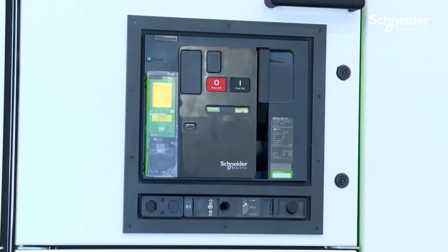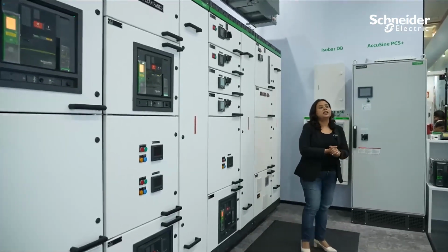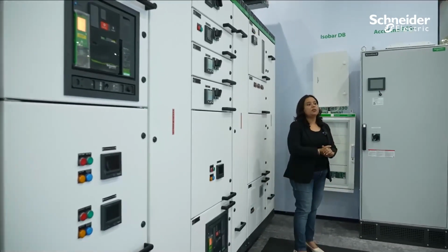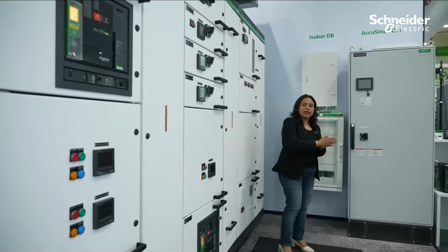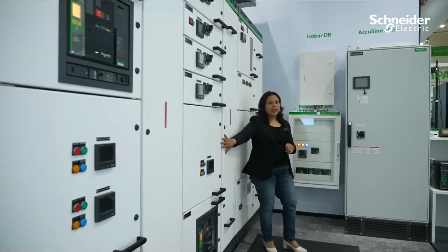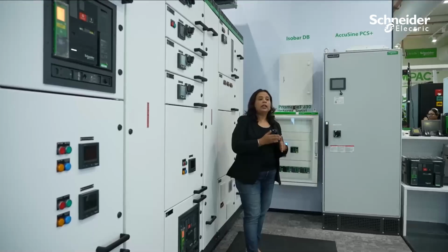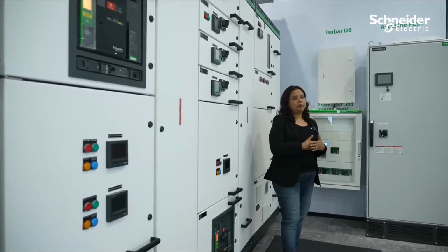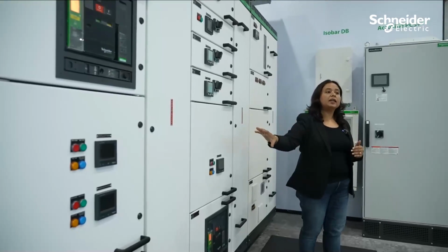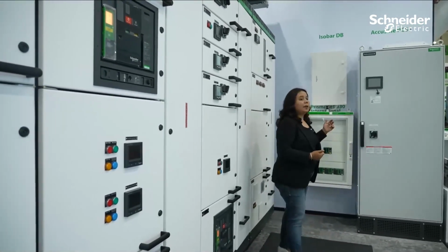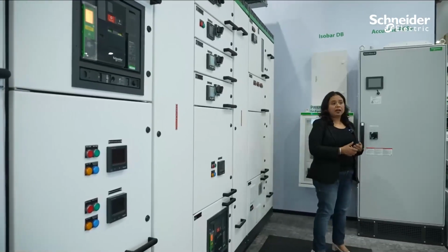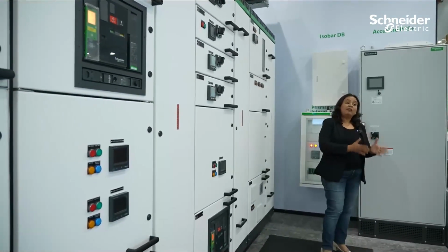While we talk about the complete distribution system, I also want to highlight that when it comes to harmonics, we have the complete solution integrated in our panel itself, from harmonic identification till mitigation, and sometimes completely discarding harmonics. We have high-end PQ meters, power quality meters, panels which are active harmonic filters, and panels which are power factor correction panels, helping in very critical applications like data centers, healthcare, and industries where you cannot afford any disturbance in your network.